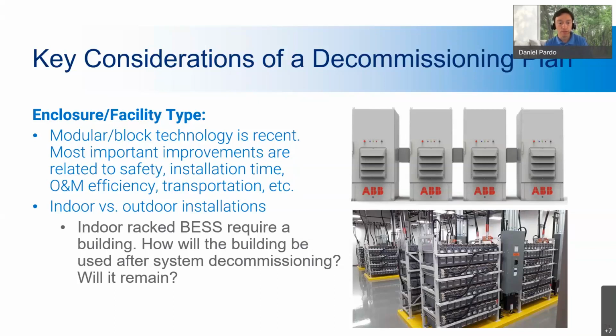There is another type of storage facility, shown in the lower image, called an indoor installation. In this type of battery system, there are no blocks or containers, but battery racks within a building. These buildings usually require an HVAC system because the batteries need to be temperature controlled, and there's also a foundation, a control room, and additional things in that building.